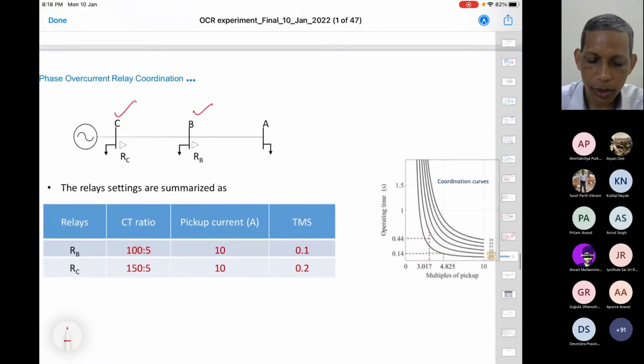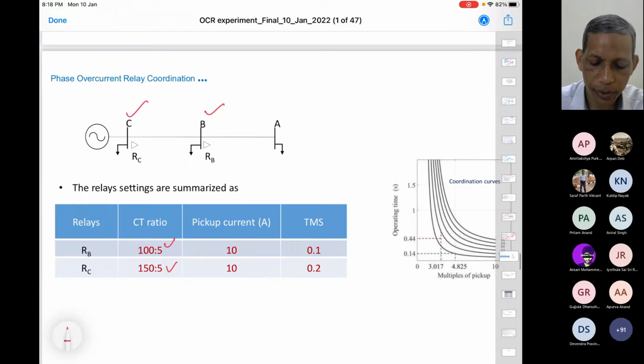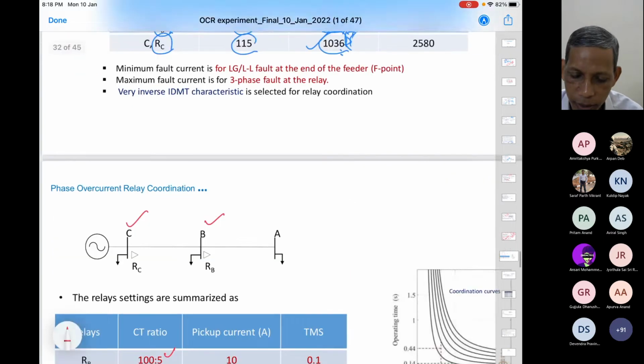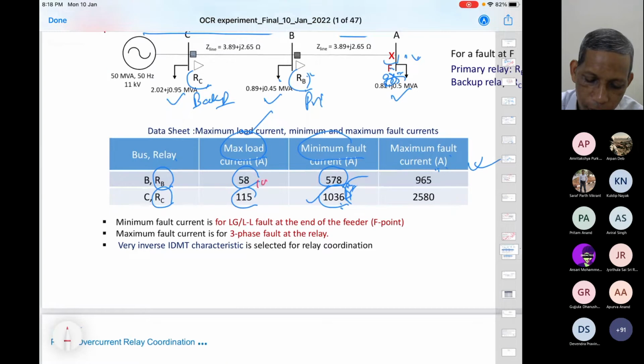So we got CT ratios of 100:5 and 150:5 selected. I told you how to select the CT based on the current level. In one case, we got something less than the current level, say like 58 amperes, so I pick up the 100, and here it is 150:5. Here 100:5. So that is the CT selection. Then the pickup current setting is based on the corresponding full load current. We consider the minimum fault current and the high full load current, the maximum current. We select 10 ampere here, 10 ampere here.